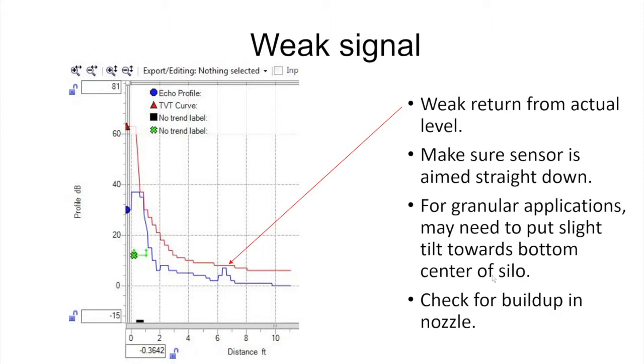So what can cause a weak signal? First thing we want to look at is to make sure that the level sensor for liquid applications is pointed straight down so we bounce straight off the liquid level back up to the receiver. For granular applications I'd say probably 80 percent of the time I do point straight down, but there are some instances where you want to tilt the sensor towards the bottom center of the silo to get a stronger return.